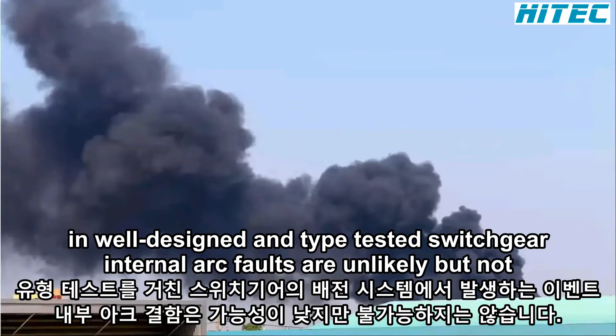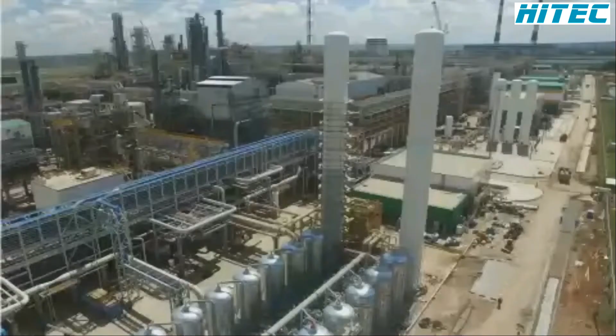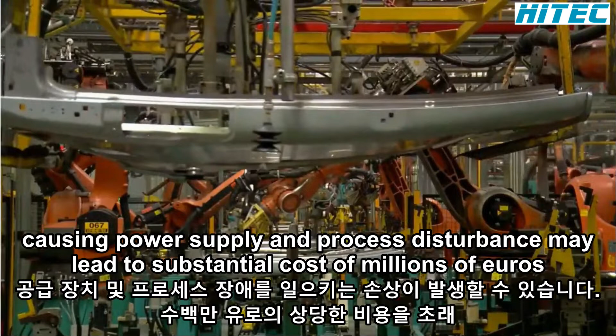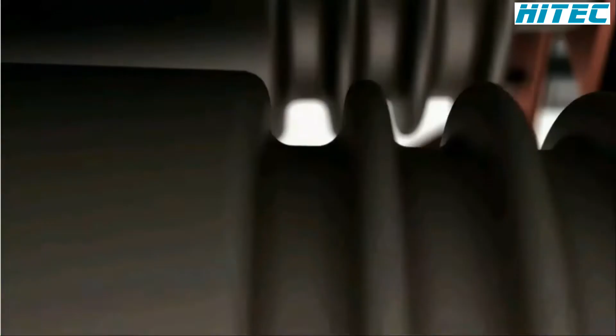Arc flash faults are the most devastating events in power distribution systems. In well-designed and type-tested switchgear, internal arc faults are unlikely, but not impossible. Mostly, they are linked to human interference or environmental causes. Typical internal arc classified switchgear can prevent operator injury under normal operating conditions. However, it does not protect the equipment from irreparable damage and does not eliminate all the secondary hazards caused by an arc flash. The damage causing power supply and process disturbance may lead to substantial costs of millions of euros.